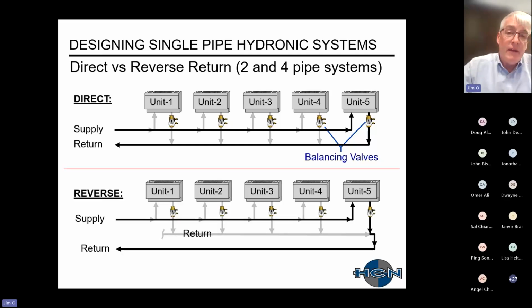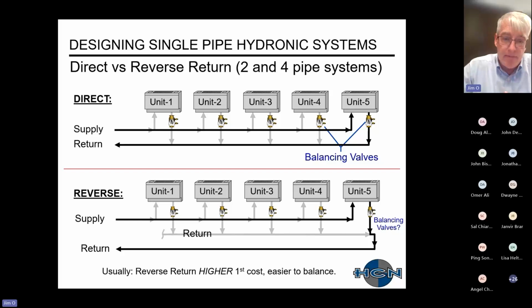The other type of piping distribution system is what is called reverse return. What you can see is basically the supply piping is the same, but now we have changed the return piping. What ends up happening now is that the supply goes to the first unit, so it has a shorter supply, and then when it goes to the return, it has the longest return. Usually the reverse return, because you're adding more piping, has a higher first cost. Though because all the piping is technically close to being equal, it is easier from a water balancing standpoint to balance that.